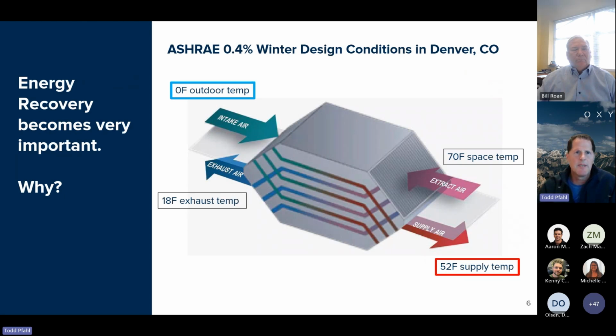So how do we help out the energy efficiency of heat pumps? One easy way to do that, a great energy efficient way to do that, is to raise the entering air temperature going into that heat exchanger so the heat pumps and the compressors don't have to do as much work. So we can do that with readily available air-to-air heat exchangers. So these are very simple devices where we're just transferring energy from one airstream to the other. In this example here, we're taking the relatively warm space air temperatures of 70 degrees and transferring that to your 0 degree outside air temperatures.